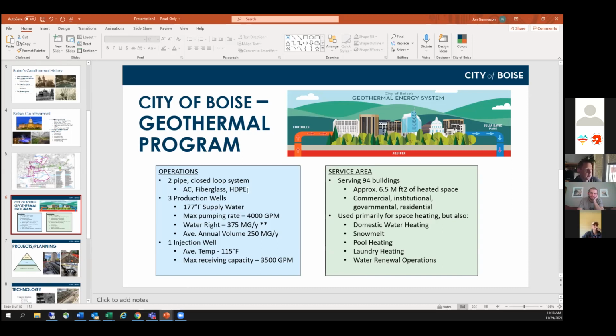I mentioned we have 3 production wells producing 177-degree water. These 3 production wells can max out at about 4,000 gallons per minute. Right now we're peaking at about 2,000, so we almost have double the pumping capacity of what we're currently serving.